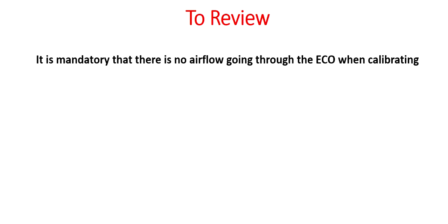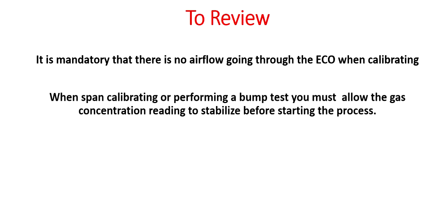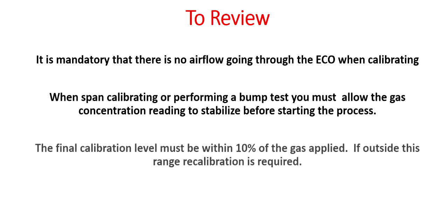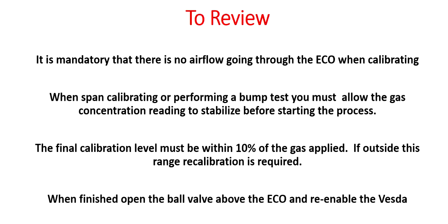To review, it is mandatory that there is no air flow going through the ECO when calibrating. When span calibrating or performing a bump test, you must allow the gas concentration reading to stabilize before starting the process. The final calibration level must be within 10% of the gas applied. If outside this range, recalibration is required. When finished, open the ball valve above the ECO and re-enable the VESDA.